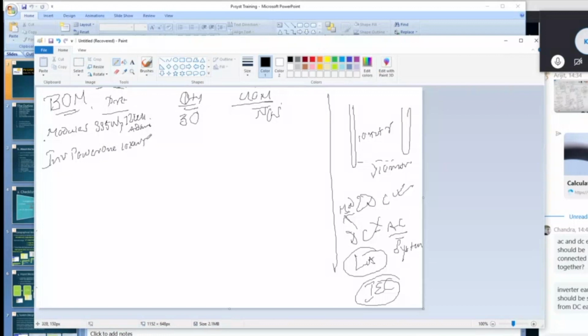10 kilowatt peak, 3-phase inverter, one number. Next is structure, HDGI, 85 microns. It is always in kgs. Generally, we have discussed it is between 45 to 65 kgs. We are taking 55 as average, so 55 into 10, 550 kgs of structure we would be requiring.